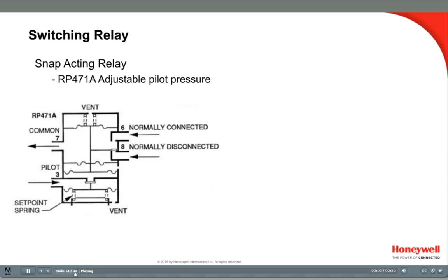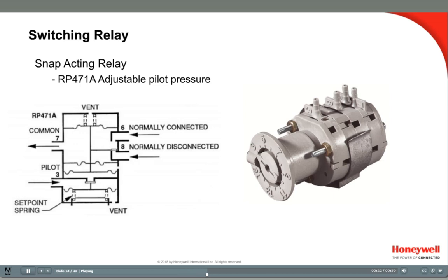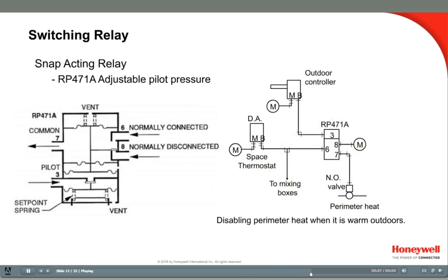The RP-471 is a switching relay similar to the RP-670A. It has one single-pole double-throw relay, but the difference is that it has an adjustable setpoint. It will switch ports at a specific pressure, providing an additional level of control switching logic. The switching setpoint is adjustable between 3 and 15 psi, with about a half psi differential. Just like the RP-670, port 3 is the pilot port and 7 is the common port, with 6 and 8 being the switched ports. In this example, the switch is interrupting the thermostat branch line going to a heating valve, disabling the valve when the outdoor temperature is warm, and additionally applying full main air to hold the valve closed.